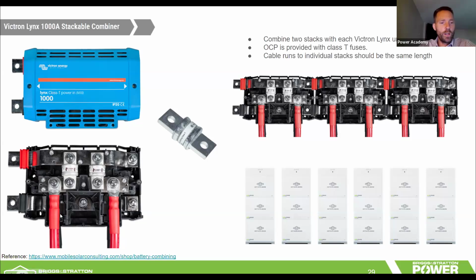What you can't see very well here is that the negative battery cables are attached to a 1,000 amp bus bar on the bottom, and these units are stackable, so you'll put the inputs of the second on the outputs of the first, and so you can stack these. If you want to do 6 stacks, 3 of these would give you a 1,000 amp combiner with individual overcurrent protection on each one of your battery inputs. There's a space here between these, and each battery stack has an individual fuse on it, leading to that overall positive bus bar, 1,000 amps on the top, and the negative bus bar runs underneath on the bottom at 1,000 amps as well.